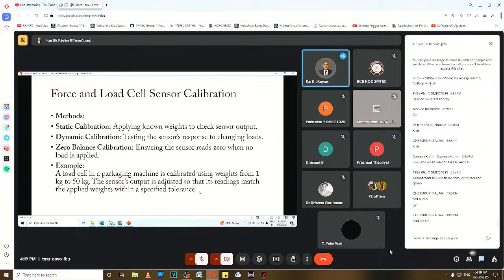Next, force and load cell sensor calibration. There are three methods used in load cell sensor calibration. First one is applying known weights to check sensor output. Next is dynamic calibration, and the third one is zero balance calibration. Dynamic calibration tests how the sensor responds to changing loads. Zero balance calibration ensures the sensor reads zero when no load is applied. Example: a load cell in a packaging machine is calibrated using weights from 1 kg to 50 kg. The sensor's output is adjusted so that its readings match the applied weights within a specified tolerance.